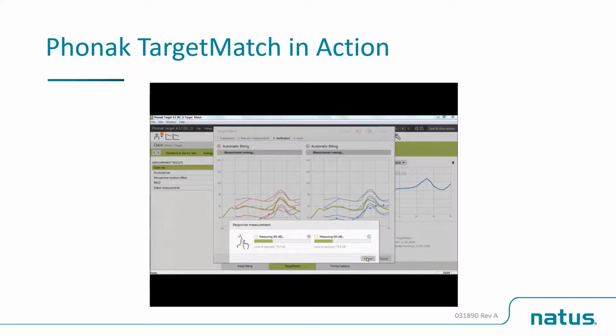Now as we move on, it's doing a first measurement of the soft, average, and loud sounds. And then it's going to go back and work to match to those targets after it has measured the initial. If we had done measure only, it wouldn't go back to this matching process. Now you see it's going back to soft speech. The green active line you see is what's actively being measured, and you can see it adjusting to the dotted line in the video to get as close to target as possible.